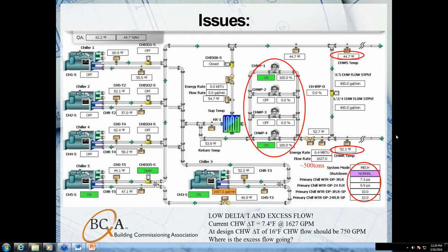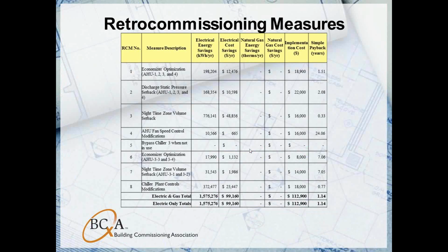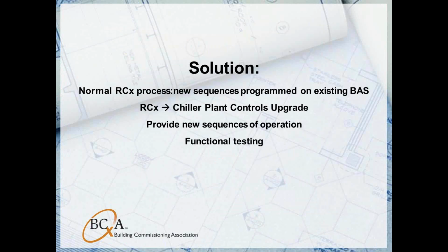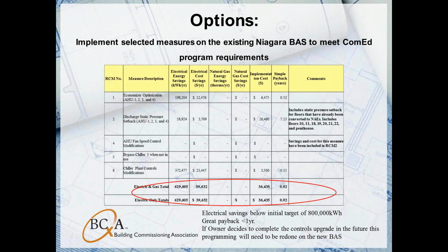So another question we had here was, was the chiller plant control upgrade price listed in the FIM table? FIM 8 shows $3,500, but the chiller plant upgrade must have been much more than that. That's correct. So as part of the retro commissioning program, you have to keep your payback below a year and a half. So for the chiller plant controls modification measure, the scope was getting all that programming updated, not the hardware portion of it. So this is just including the programming involved, and the controls contractor estimated that at $3,500. Hardware and everything, I think the price was somewhere around $40,000.